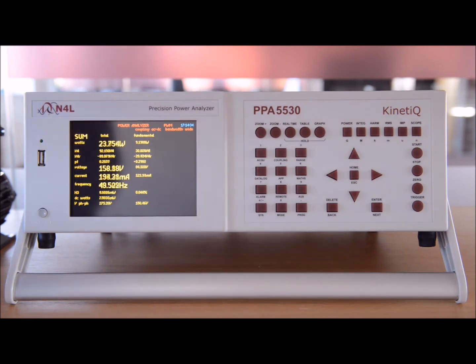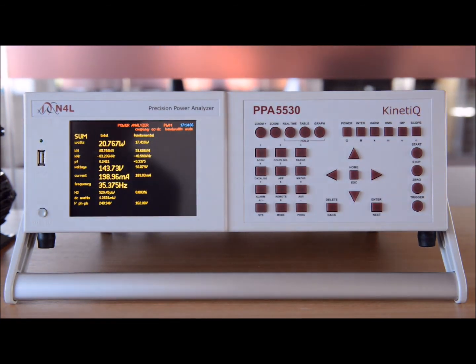We're going down to 35 Hertz now. We can see it track nicely to 35 Hertz. And it tracks no problem whatsoever. So if you are doing some dynamic testing, then the instrument is able to track that dynamic change without a problem.